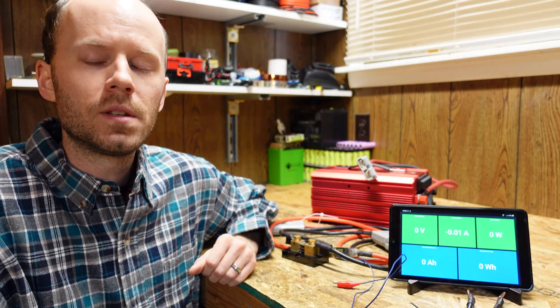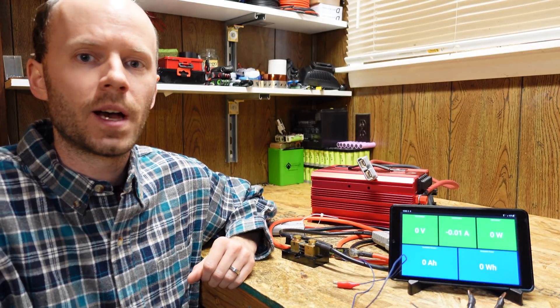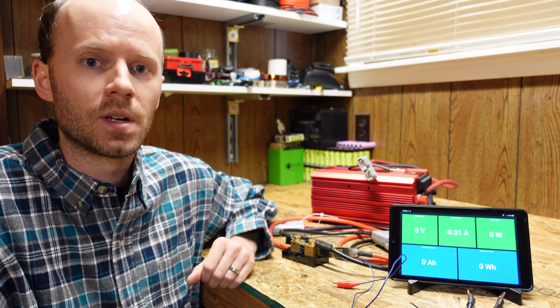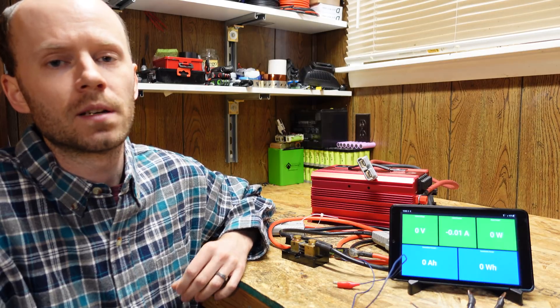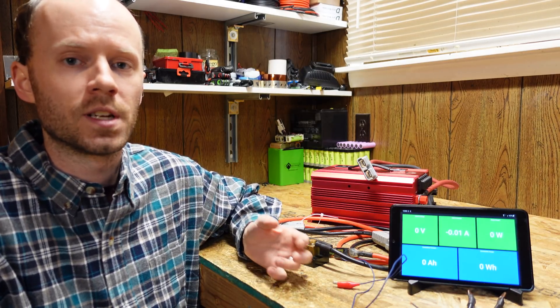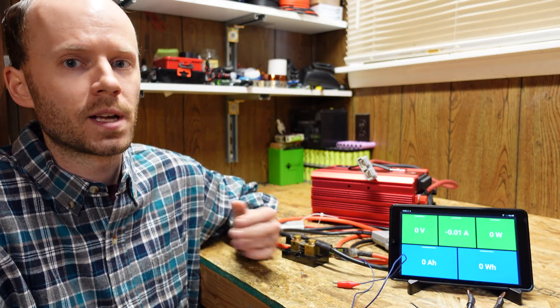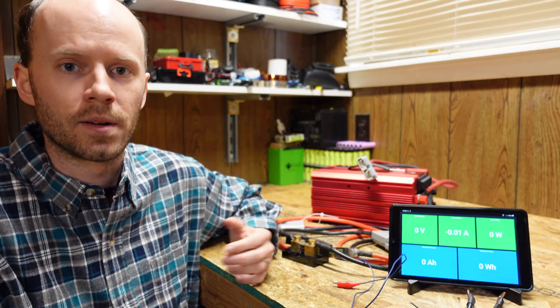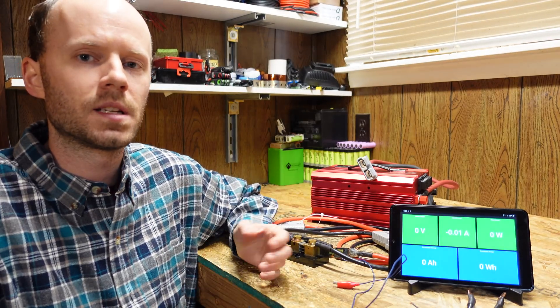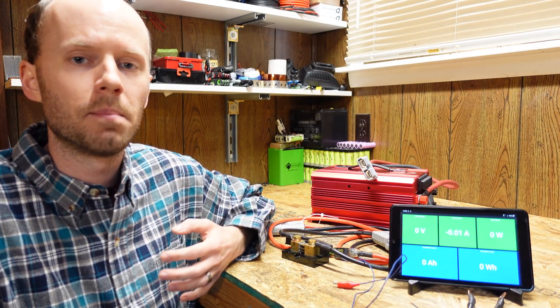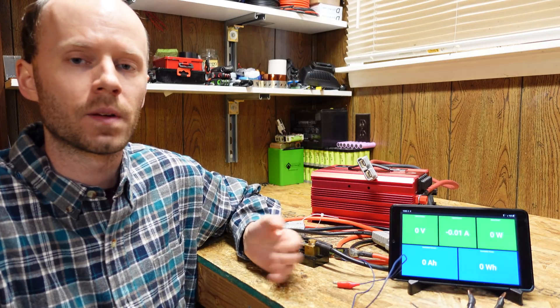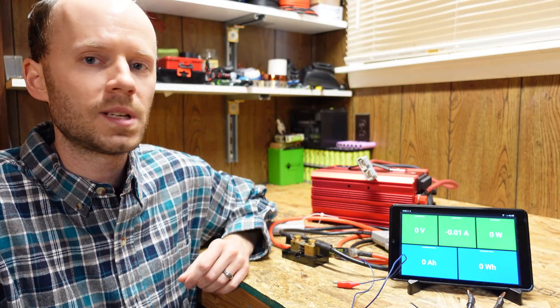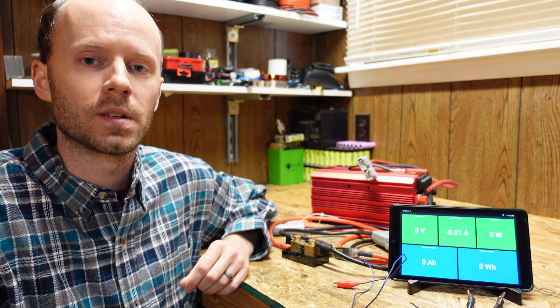What we do in these battery tests is we're charging up the battery to 100% state of charge, and then we discharge the battery down to 0% state of charge. That tells us the amount of stored power or stored energy in that battery. Every battery comes with a specific rating such as a 100 amp hour battery or a 200 amp hour battery. So what we're testing is that the discharge capacity we see during our test matches what the manufacturer is advertising on their battery and they're being truthful and honest.